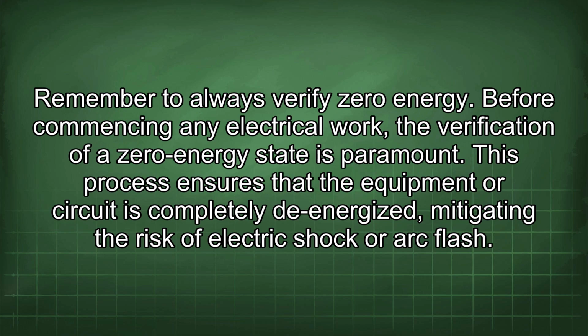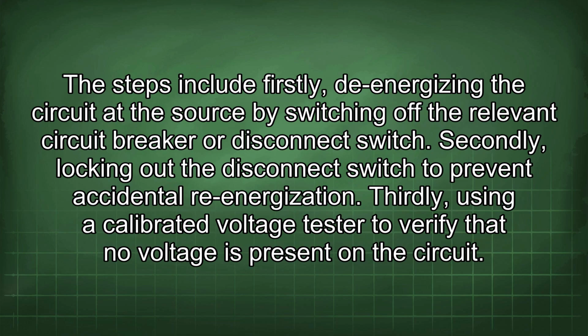Before commencing any electrical work, the verification of a zero energy state is paramount. This process ensures that the equipment or circuit is completely de-energized, mitigating the risk of electric shock or arc flash. The steps include firstly, de-energizing the circuit at the source by switching off the relevant circuit breaker or disconnect switch. Secondly, locking out the disconnect switch to prevent accidental re-energization.